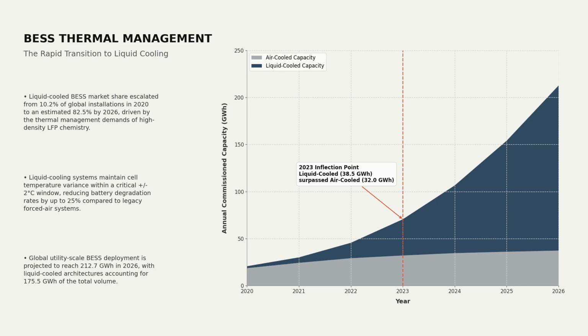Liquid-cooled architectures have escalated from 10.2% of global installations in 2020 to an estimated 82.5% by 2026. This shift is driven by the need to maintain cell temperature variance within a strict plus or minus 2 degrees Celsius window. Exceeding this thermal threshold accelerates capacity fade and risks catastrophic thermal runaway.